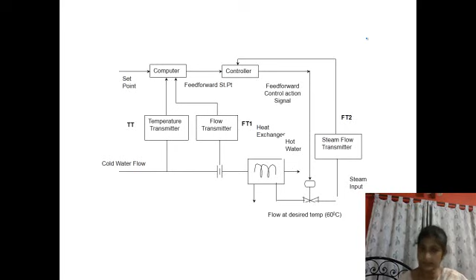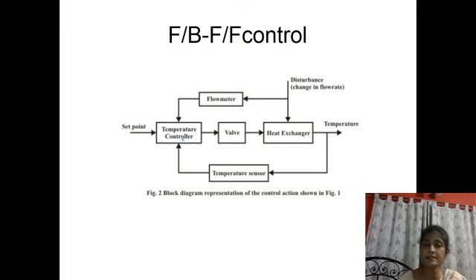Then this is the feedback part, and this is the disturbance. This is the feed forward part. So measurement of flow and temperature controller, set value, and this will adjust the energy input to the process, and the outlet temperature should be maintained at the desired value. But even then, if it deviates from the desired value to some extent, then that will be taken care of by the feedback control system. This is the temperature measurement system, and again this signal is sent to the controller.